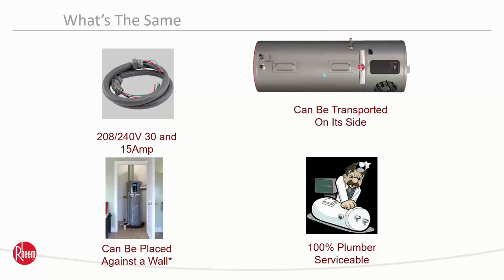Can be transported on its side. Now, this is a big deal for contractors that are using vans. You take that 80-gallon model, that's 6.5 feet tall almost. You can lay ours on its side. It's not going to hurt it. Typically with compressors and refrigerants and oils, you don't lay them on their side because then the oil settles and you have issues. It's not a problem with our unit. We've tested it. The way we've built it, it works well.